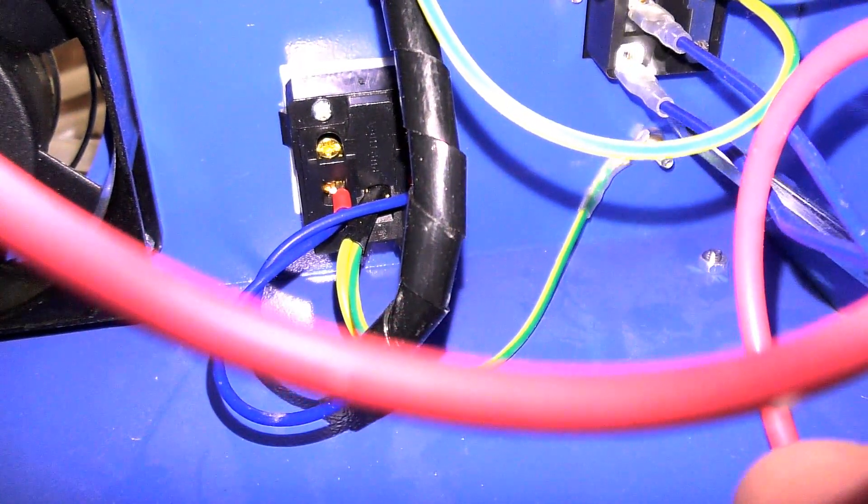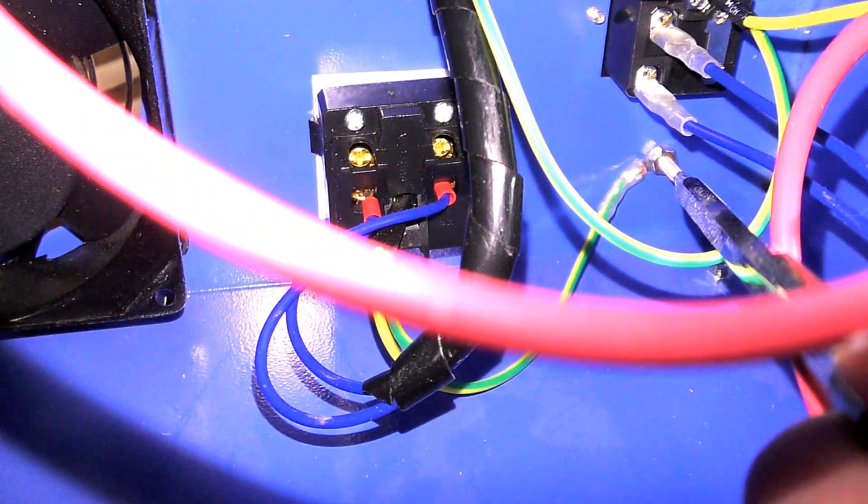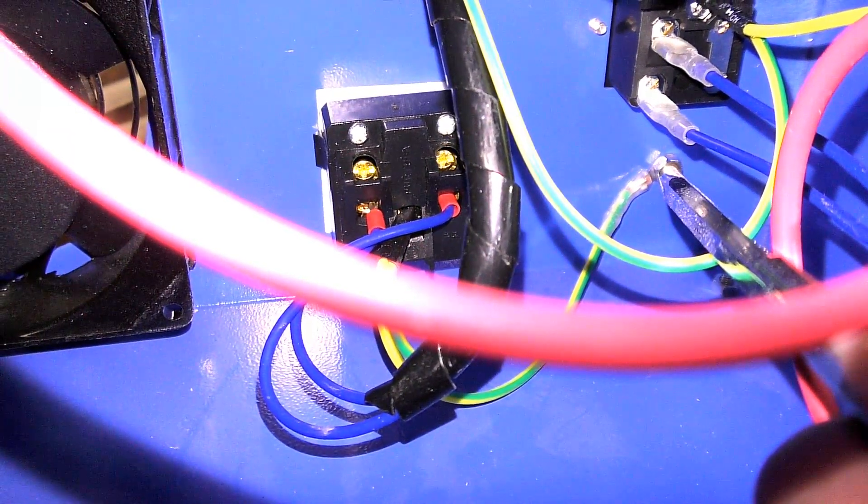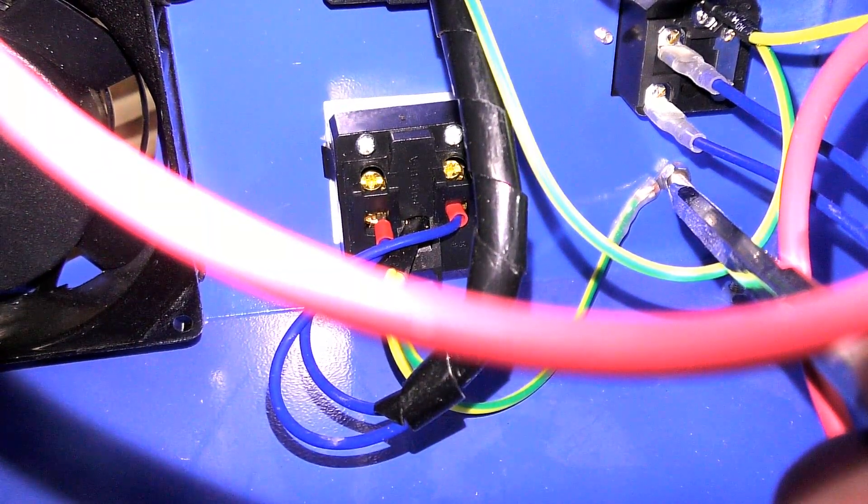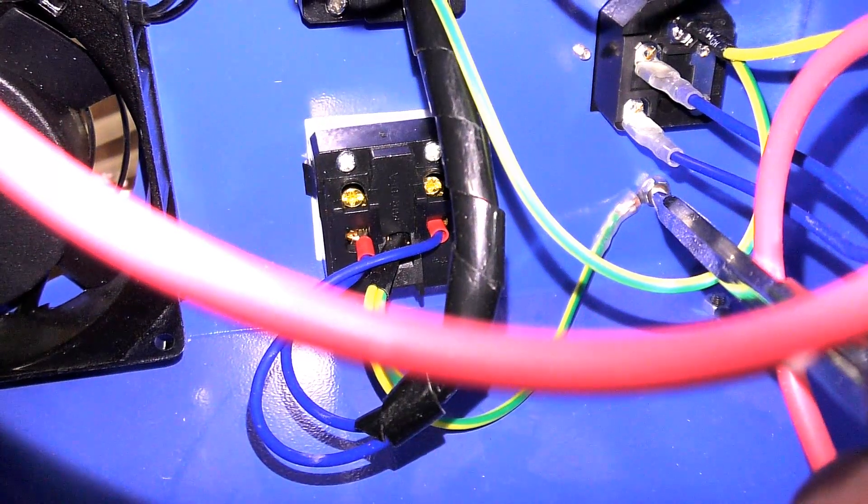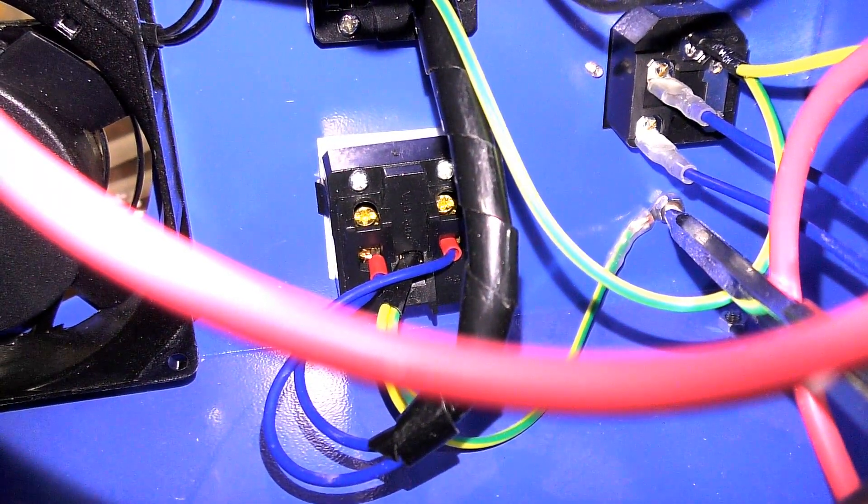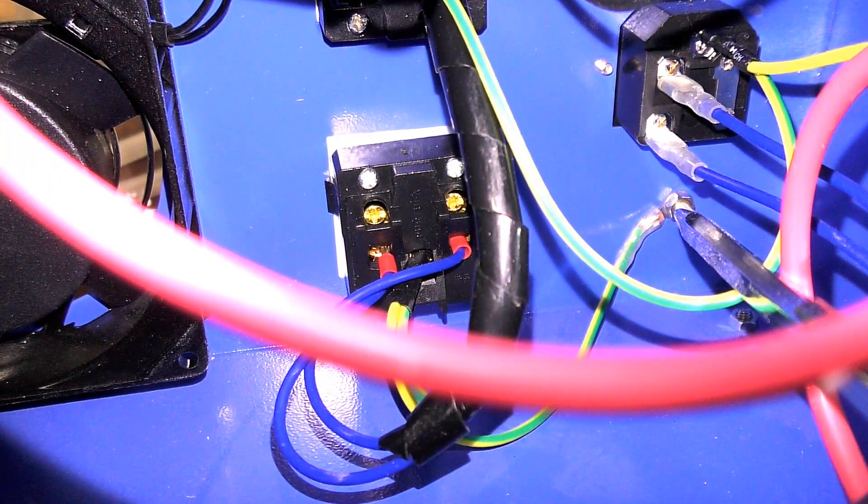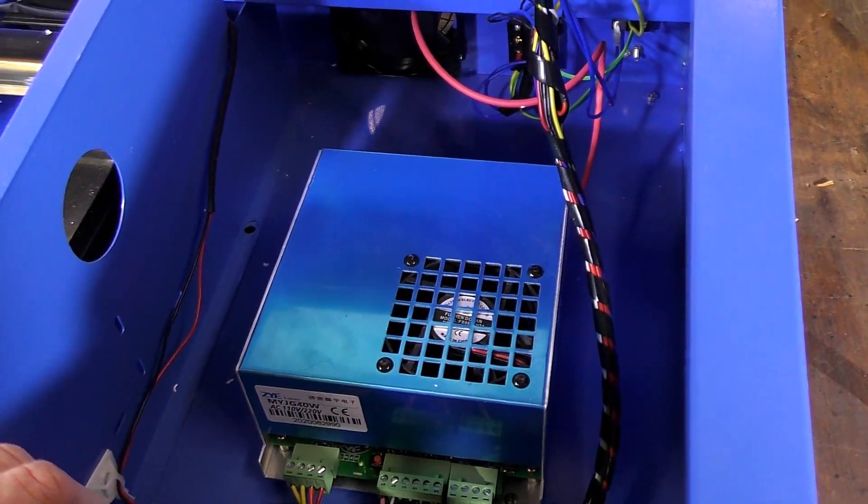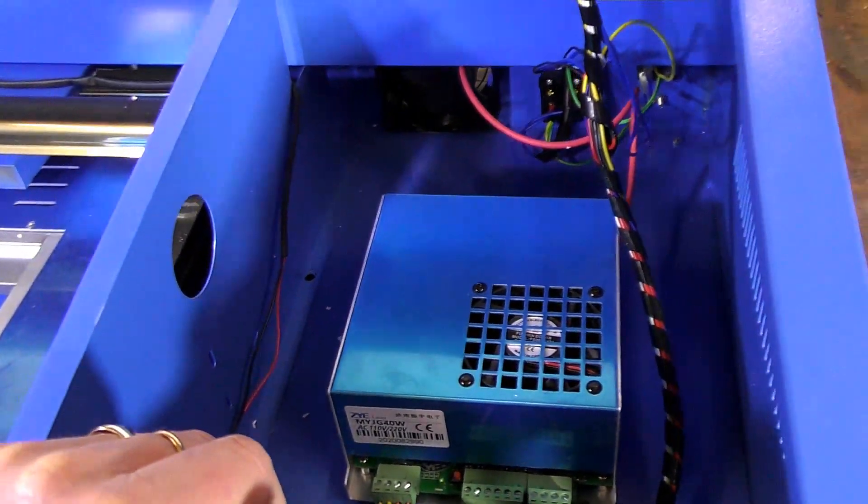That little screw there with a wire going to it, that is the main earth to the bodywork of this unit. And if you notice, it's done up or tightened up onto a painted panel. That is a serious bad earth situation.